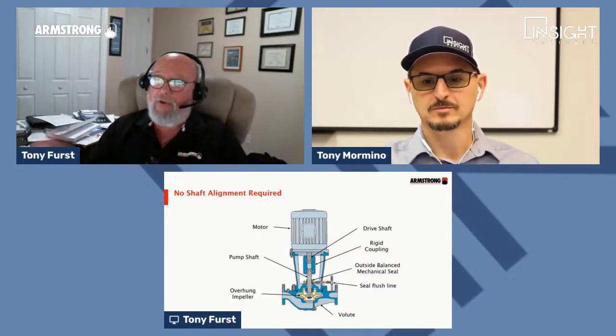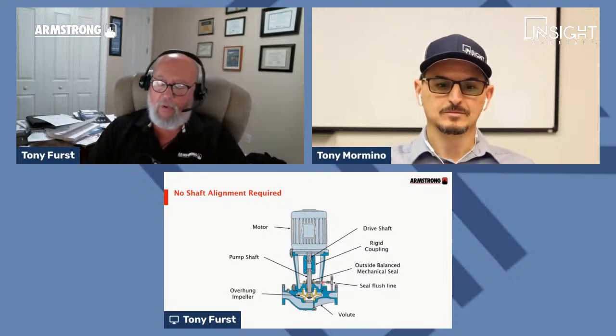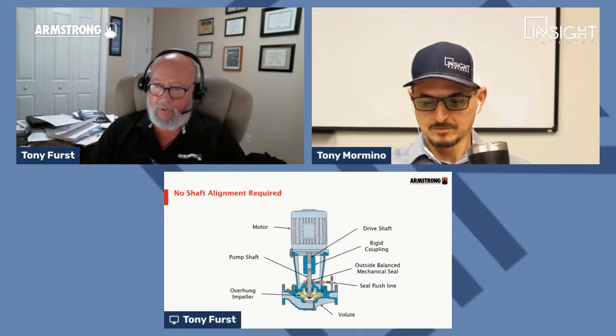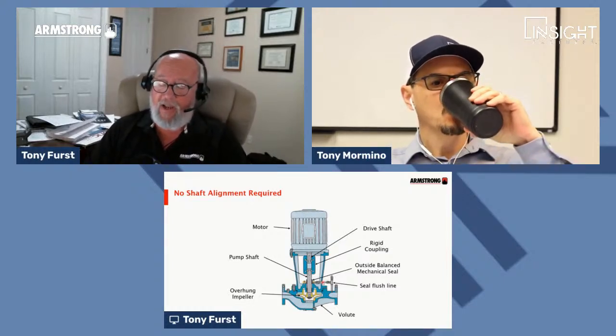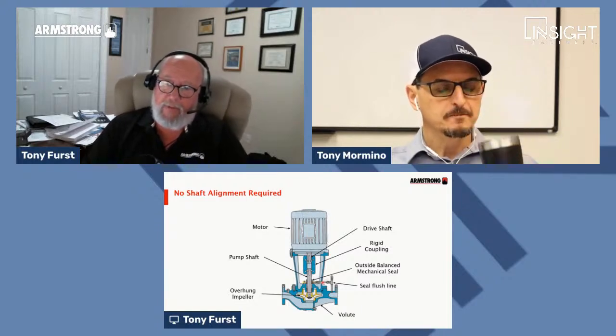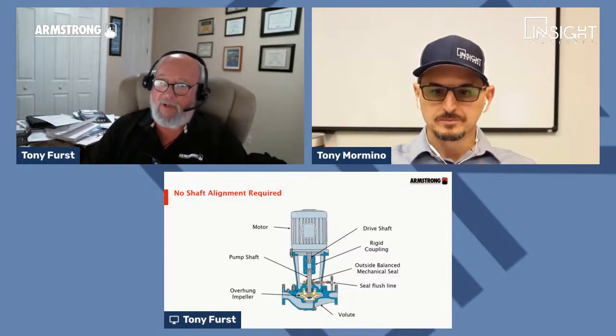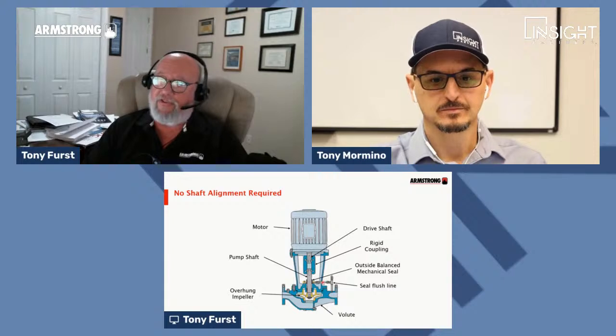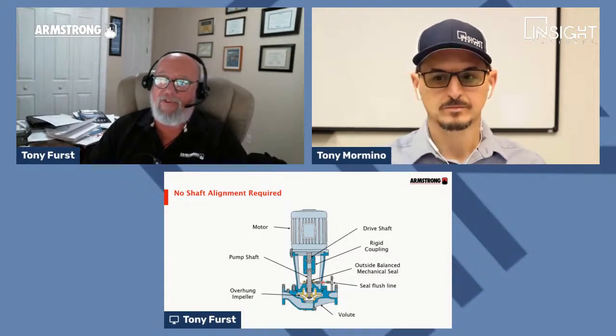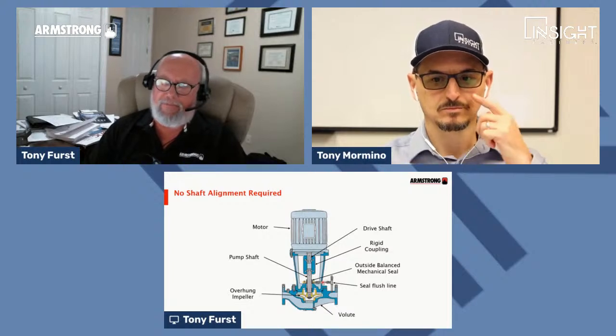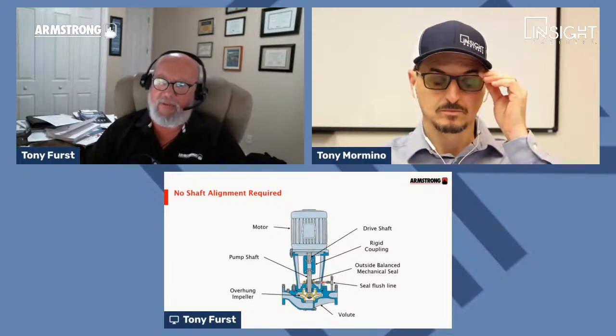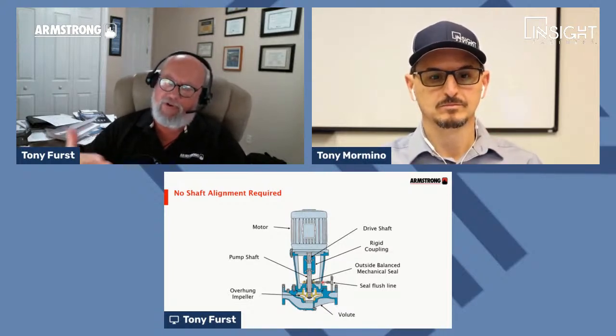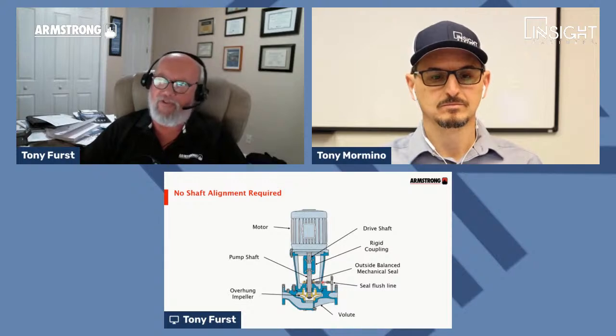Yes, and if you don't do an alignment, a couple things are going to happen. One, you'll tear the coupling up. Okay. So that's the first thing. If you're on variable speed, which pretty much every pump that we put in today is variable speed drive, the slower the speed, the worse the misalignment gets. Centrifugal force tends to mitigate some of the misalignment. The faster you go, well, as you start to slow down, that vibration gets worse.